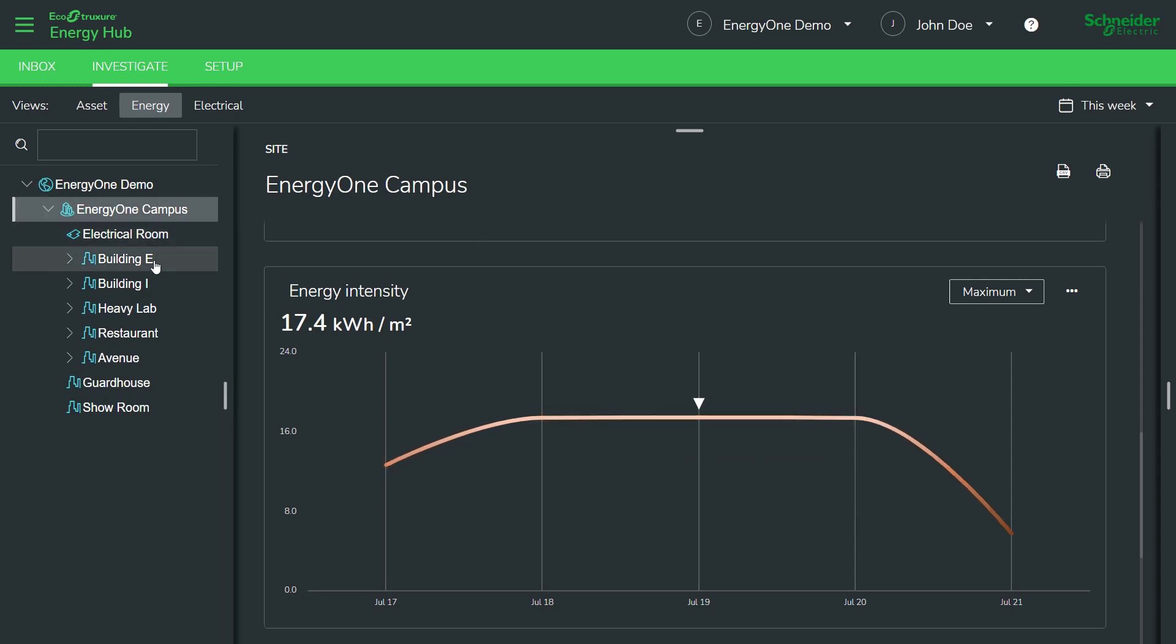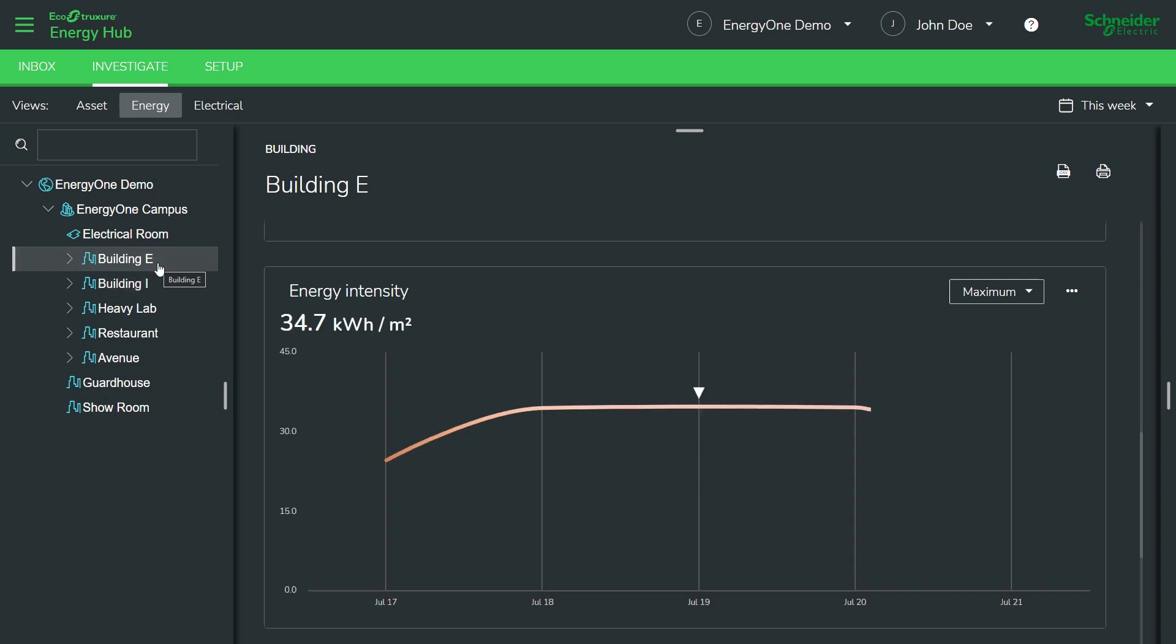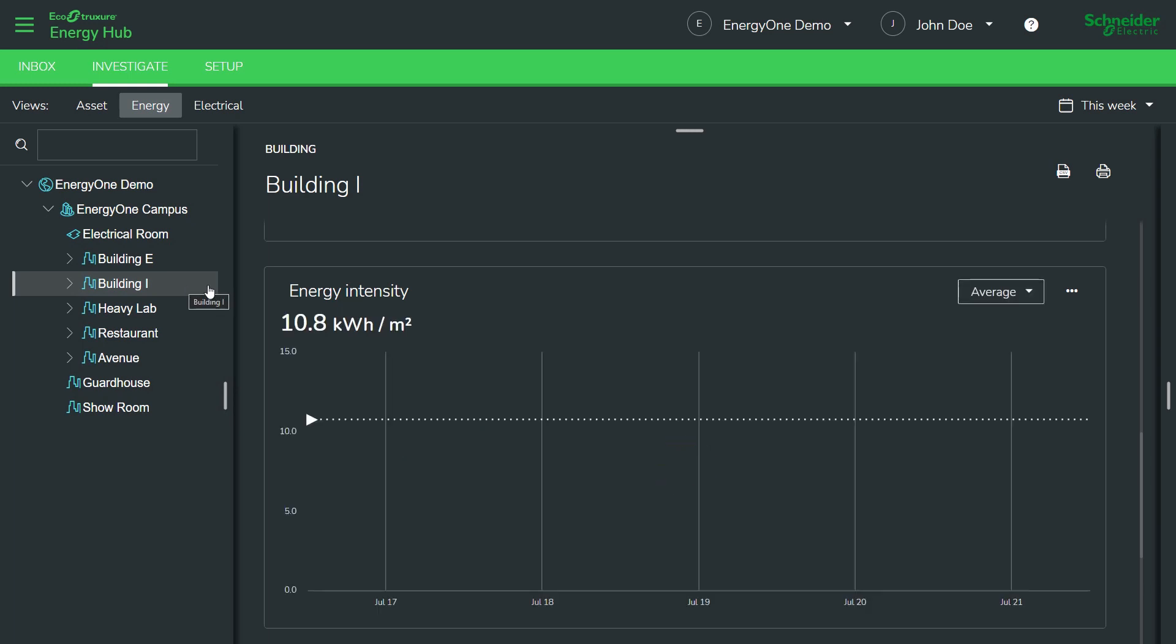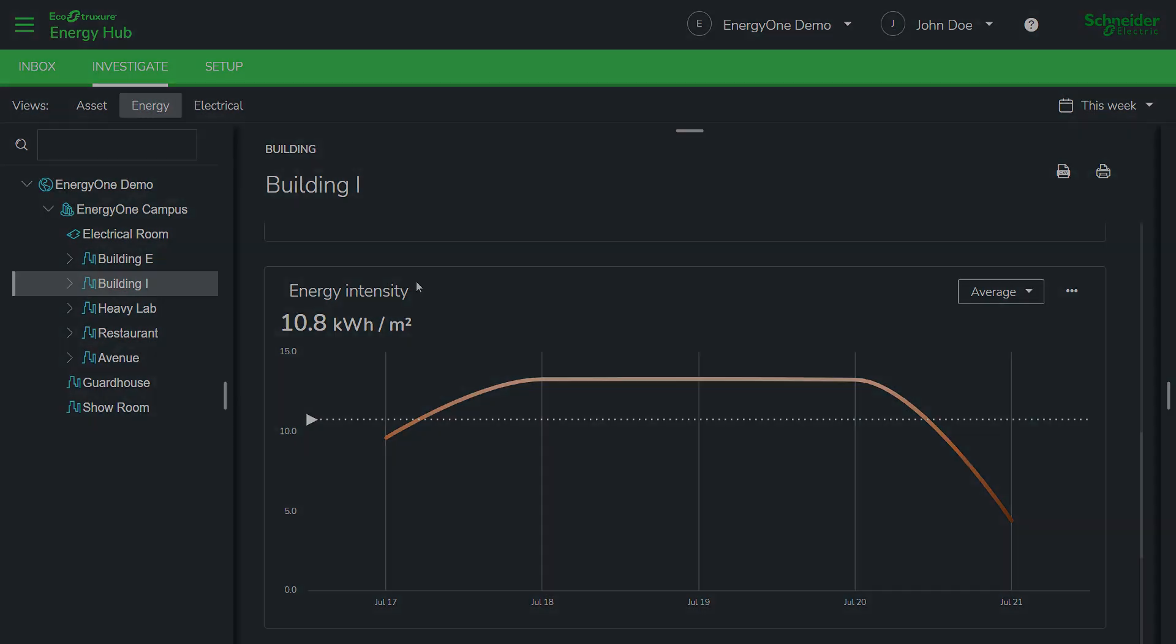You can also compare the energy intensity for, say, two different buildings. So, for building E, let's say your average intensity is 28 kilowatt hours per meter square, whereas building I averages only 10, meaning building E is a much more energy intensive building and there could be good reasons for this or it could be an anomaly that is an opportunity to get you some energy savings. Regardless, energy intensity is a powerful metric measured by Energy Hub.